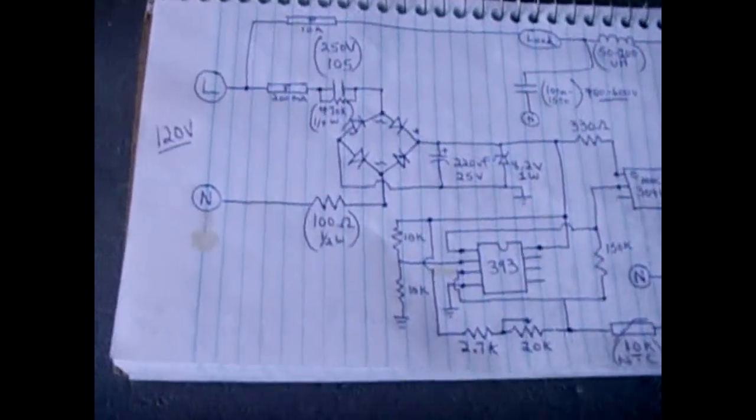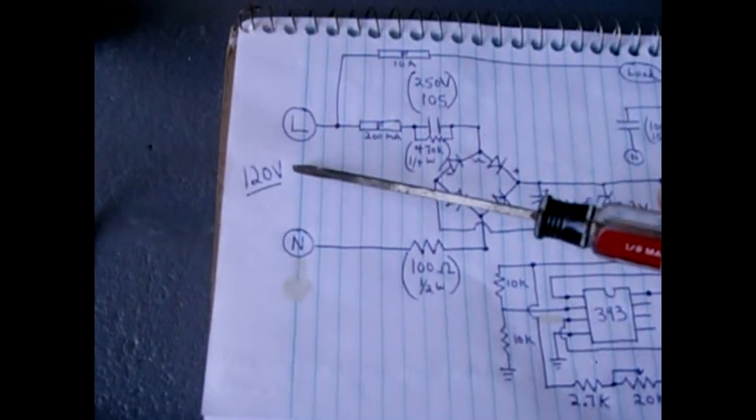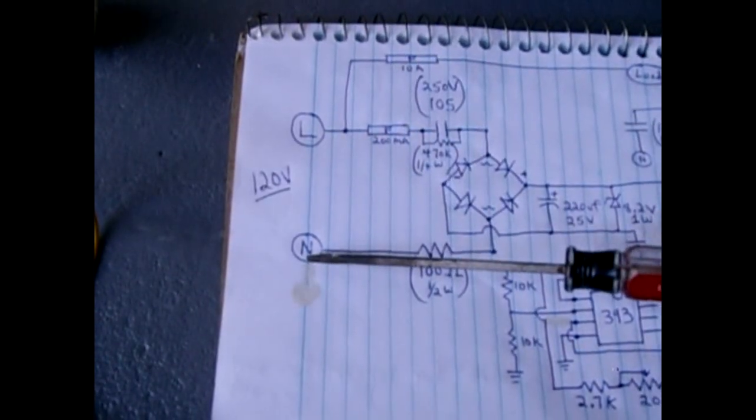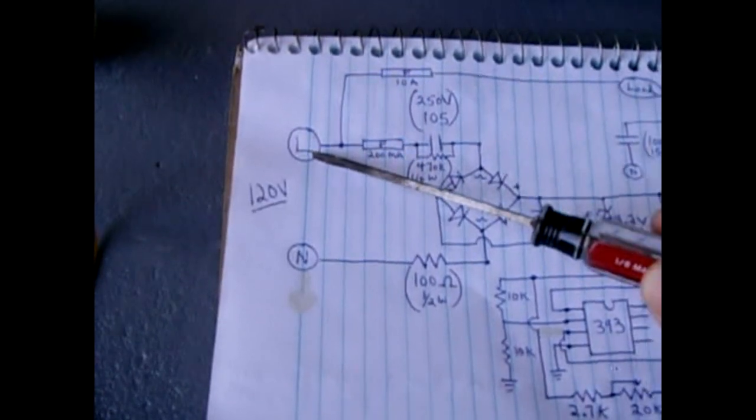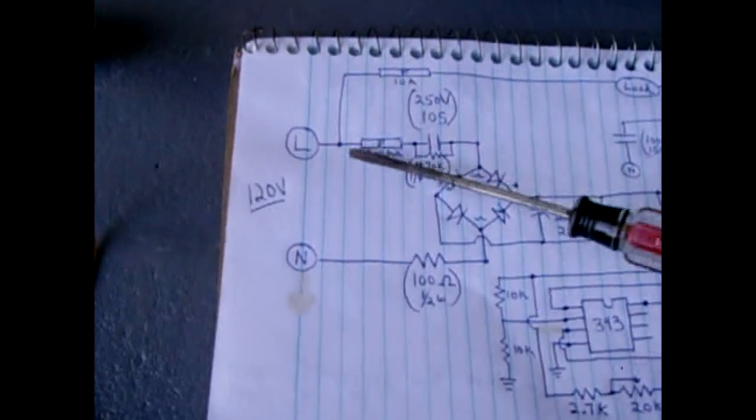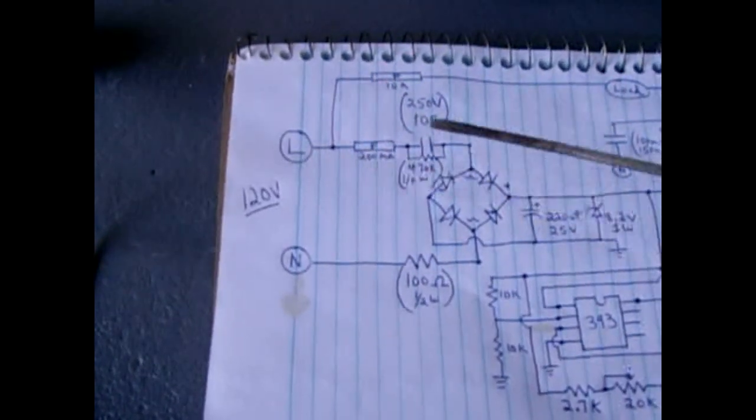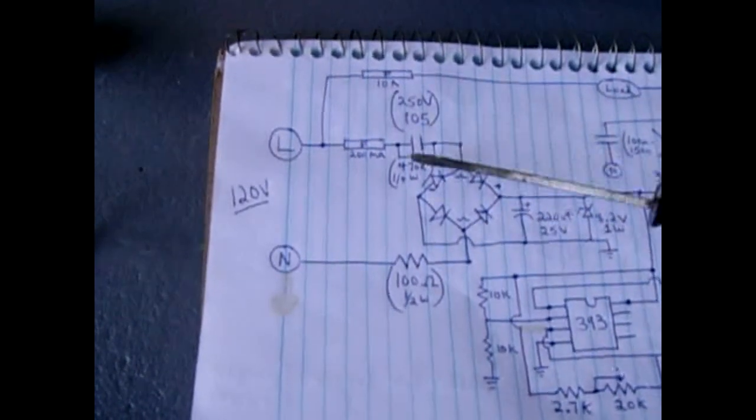The first thing I'm going to do is go over the whole schematic. Here you have your 120 volt hotline coming in and your neutral. Off of the hotline you have two fuses: one is a 200 milliamp fuse and a 10 amp fuse.